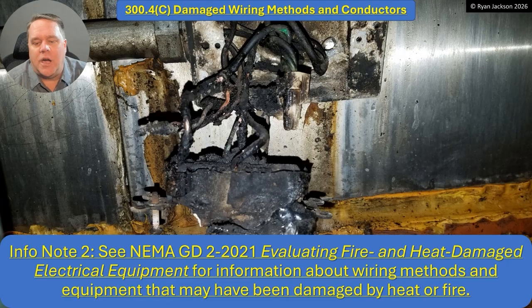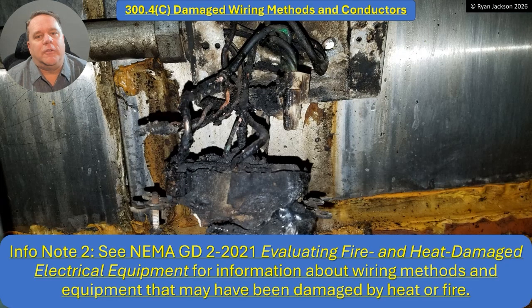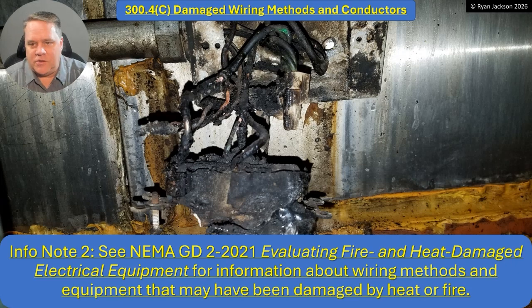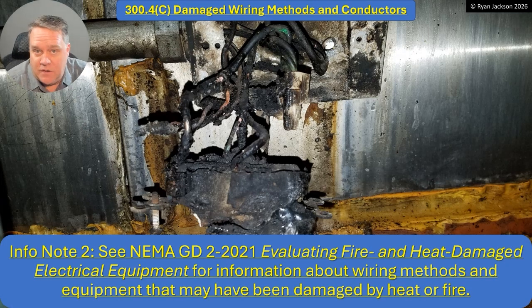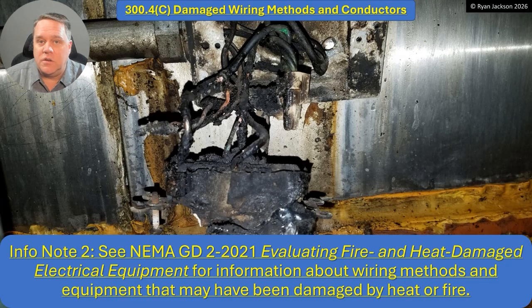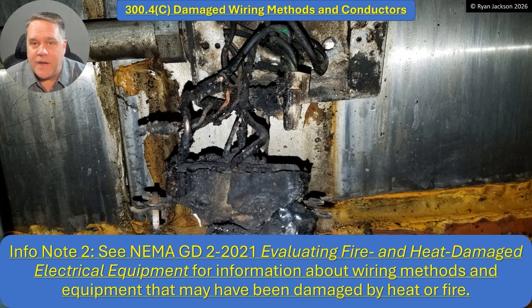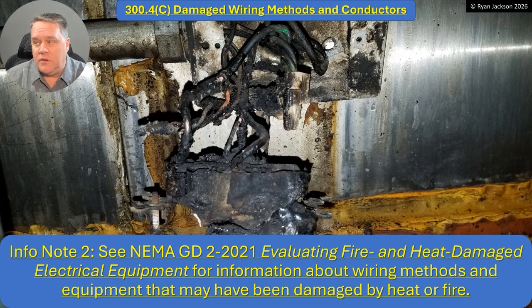The other thing added is an informational note pointing to NEMA Guideline 2-2021: Evaluating Fire and Heat Damaged Electrical Equipment — for information about wiring methods and equipment that may have been damaged by heat or fire. Clearly the wiring in a fire scene needs to be replaced. But what about the conduit, the boxes? There may be guidelines in the NEMA document, or check with the manufacturer — for example, what kind of damage does this do to the galvanization of a steel conduit where the zinc is applied?